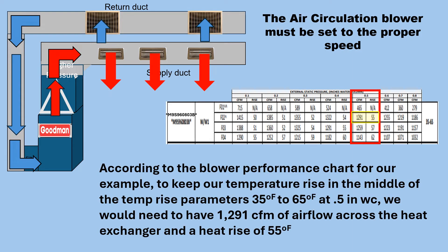According to the blower performance chart for our example, to keep our temperature rise in the middle of the temp rise parameters — 35 to 65 degrees — at 0.5 inches of water column, we would need 1,291 CFM of airflow across the heat exchanger and a heat rise of 55 degrees.